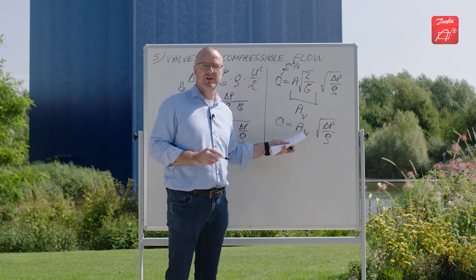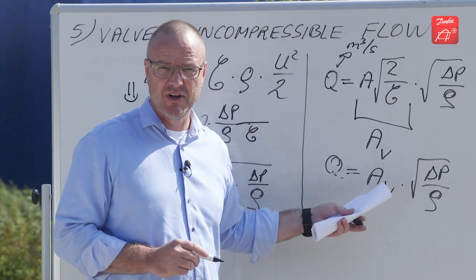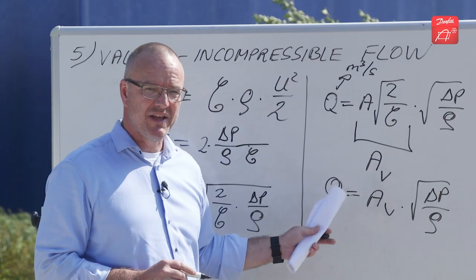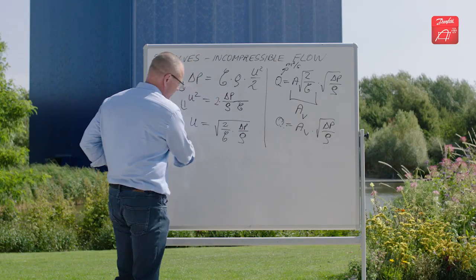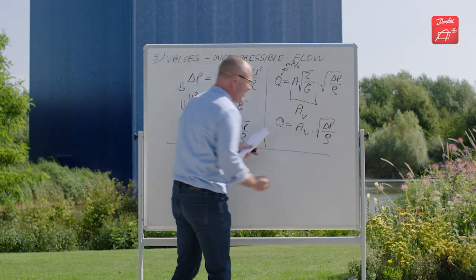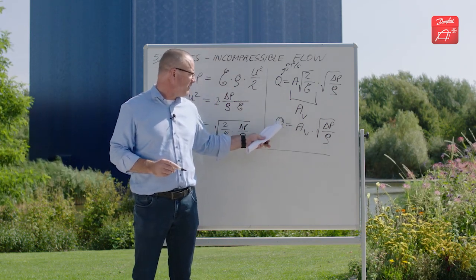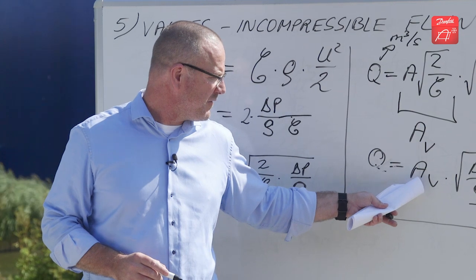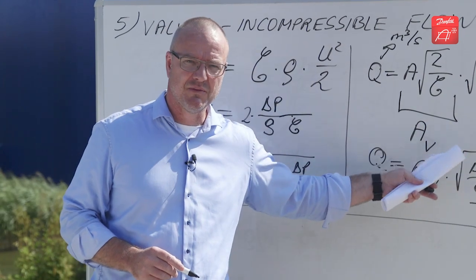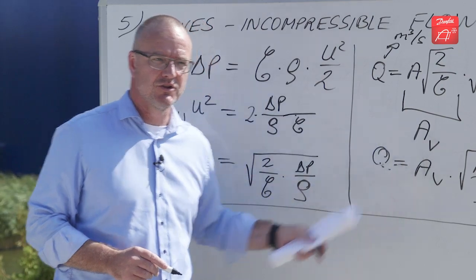Normally this flow coefficient is called KV, or if you're in the US, CV, but that's simply a matter of units. We can create a table where we express the volume flow, the flow coefficient, and delta P over rho, depending on the unit system you use.